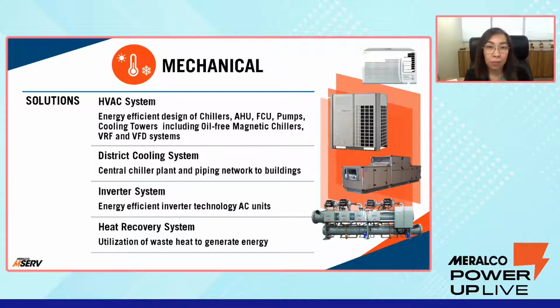For HVAC systems, we offer any of the different items available. Our go-to solution is actually an oil-free magnetic chiller, which will guarantee upwards of 20%, bringing you very good results in your energy efficiency plan. We can also do an inverter retrofit or a heat recovery system.